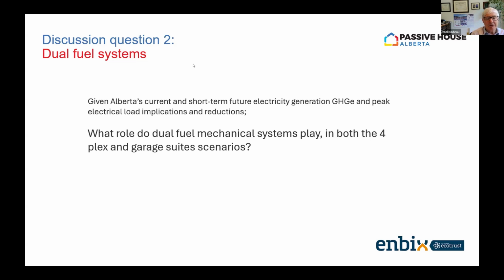The other factor, once you have a high performance building, our heat loss is only 0.9 watts per square foot, but our cooling load is 1.3 watts per square foot. So the cooling is actually the demand load, and that's the load we have to size all of our equipment for. We no longer consider heating when we're sizing the equipment, it's all about cooling now. And we substantially reduce our cooling load by just having very low solar heat gain windows, which is the cheapest option you can possibly do to lower your cooling loads.